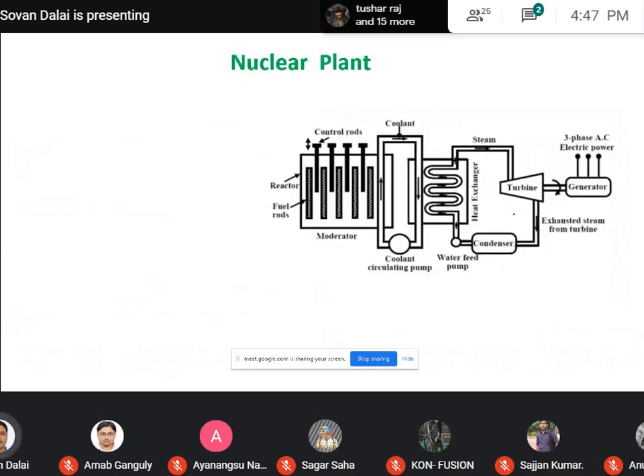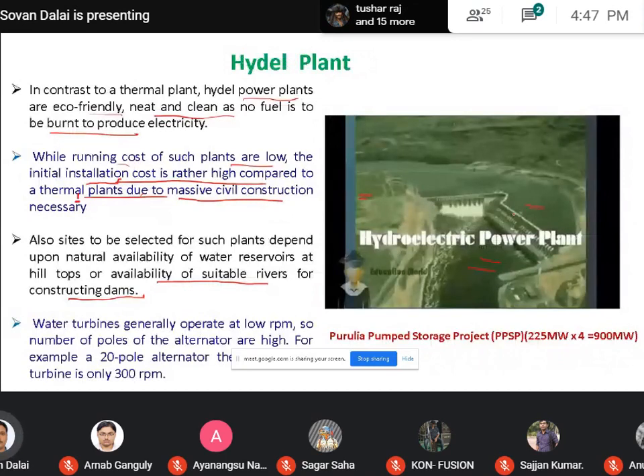In most cases of thermal power plants, these are 2 pole alternators, and a 2 pole alternator runs at 3000 RPM. But in the case of a hydel power plant, the alternator generally has a higher number of poles due to the low speed of the water turbine. So if the number of poles is 20, that alternator rotates at 300 RPM. I may want to mention that in West Bengal one hydel power plant is in Purulia, called the Purulia Pump Storage Project. Here the total number of units available is 4, and each unit has a capacity of 225 megawatts, so a total of 900 megawatt capacity for the Purulia Pump Storage Project.